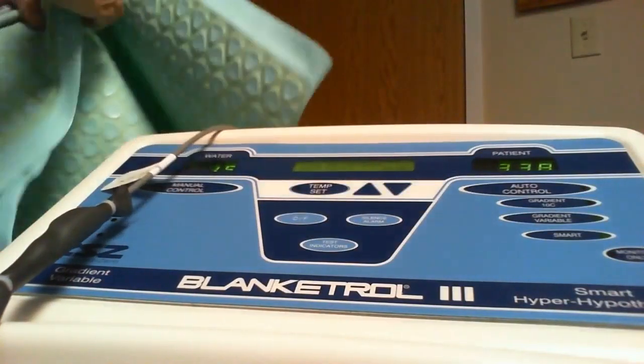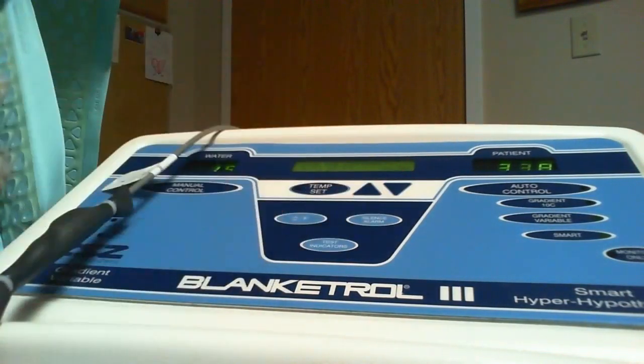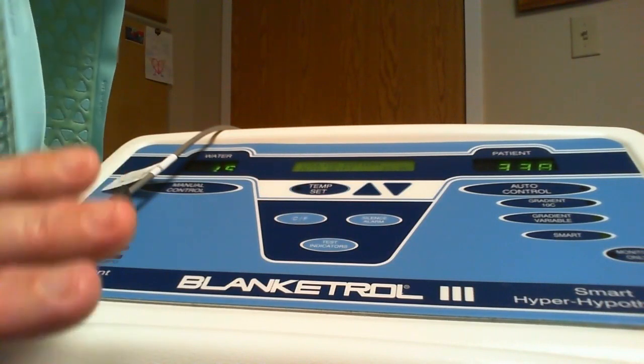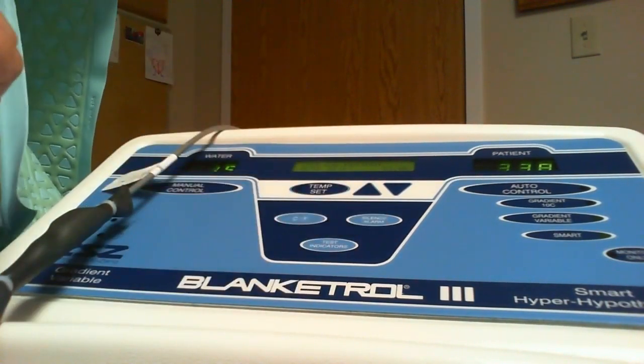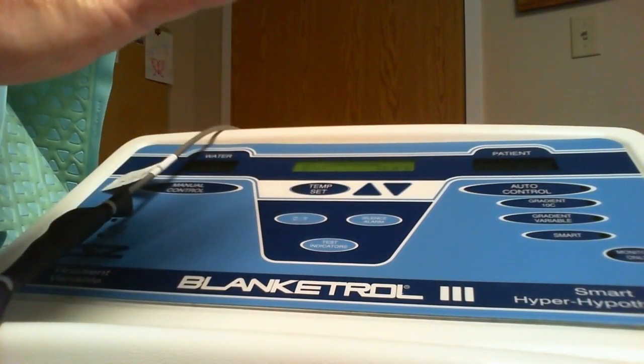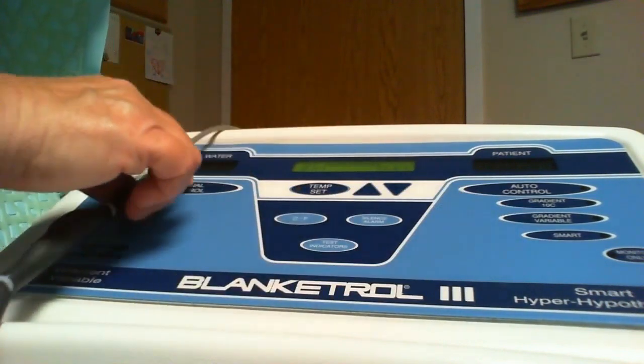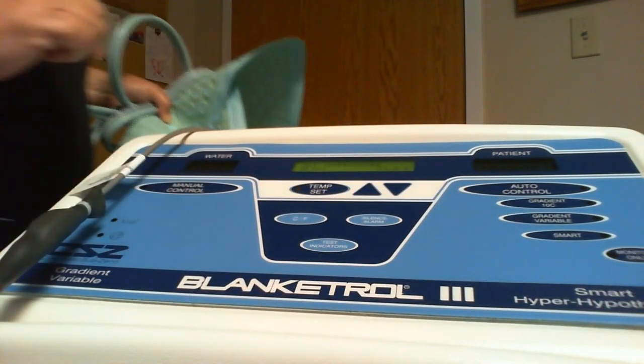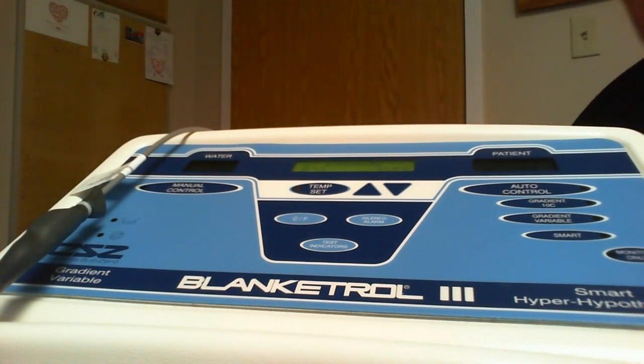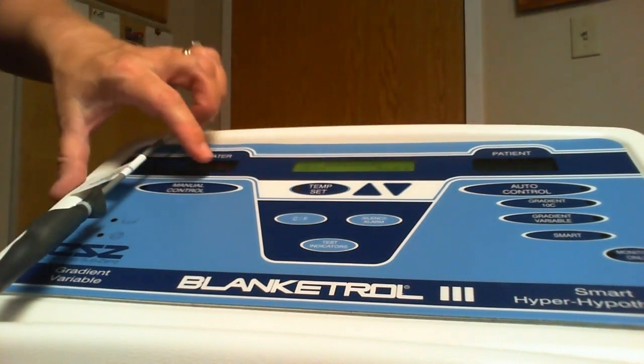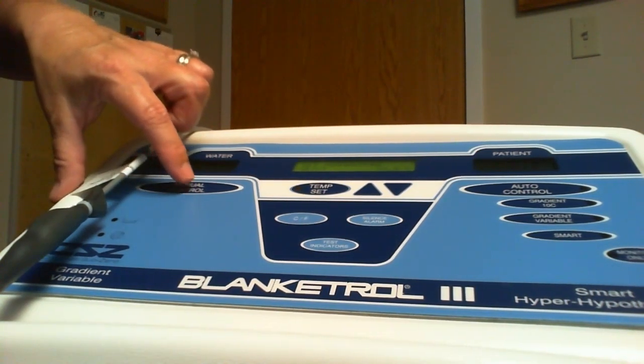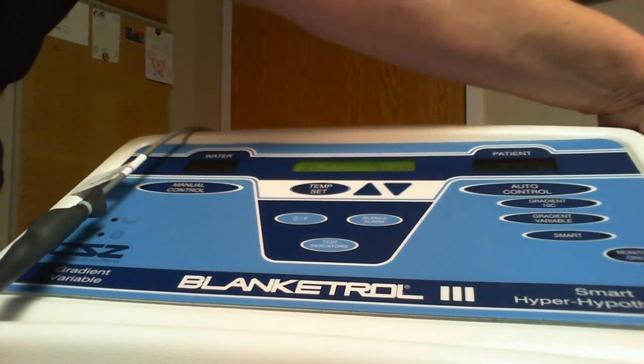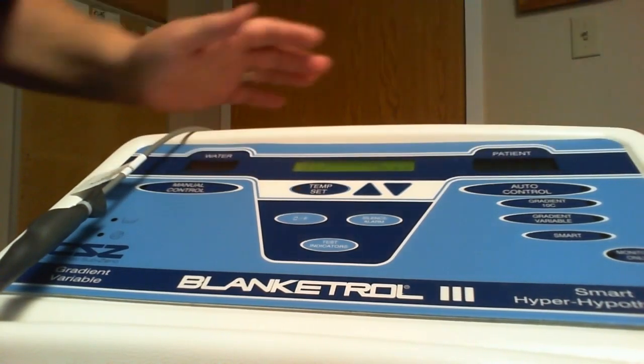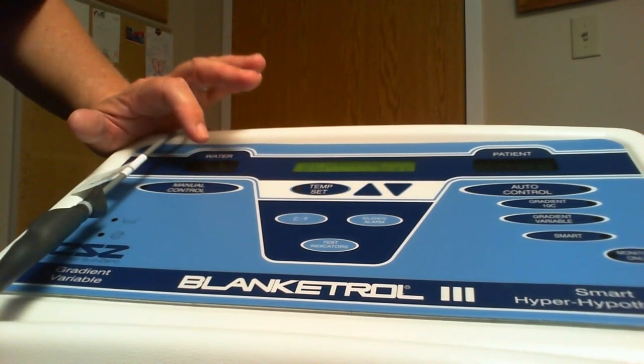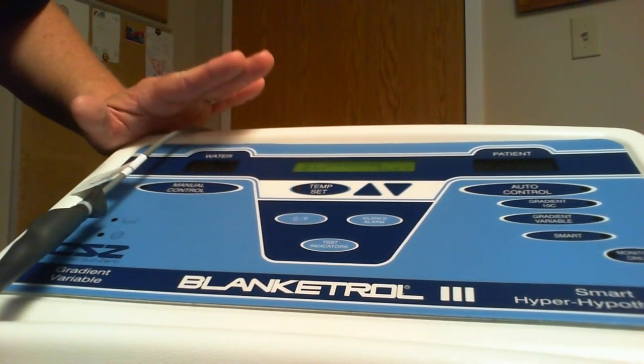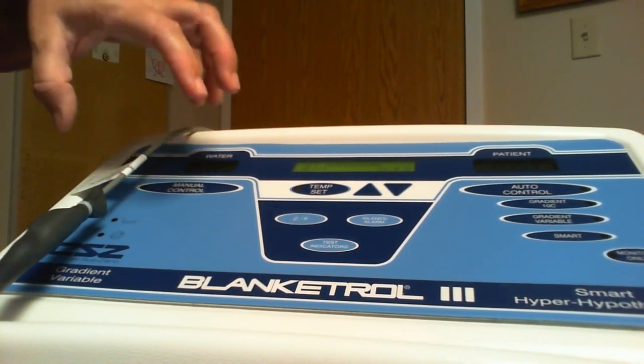There is also a silence alarm if you can't figure out what is happening and it may be distressing you or the patient. You can hit the silence alarm. Temp set stops it, and then you can go to anywhere. The manual control is not something that we use in the New Brunswick Heart Center. The manual control only allows you to set the water. It doesn't even require that you have a temperature probe into the patient. Only the water temperature gets assessed. So I don't find it particularly useful.